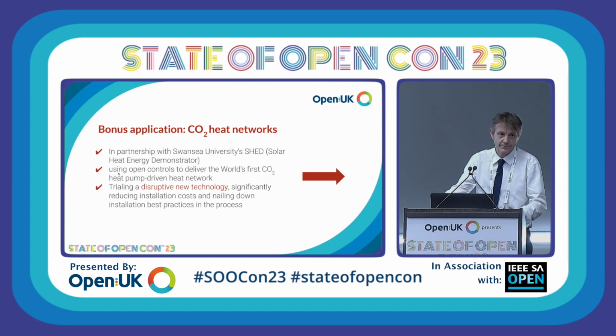In the heating world, you have consultants with professional indemnity, so they can't do anything that's not covered by regulations. We sit in a unique spot because we write the regulations. We wrote the CP1 guidance for heat networks, and we wrote the original plumbing guidance for the Institute of Plumbing. So we're in a technical position to take on these jobs, but the only way this job happens is by partnering with a university, so there's no consultants in the picture. We've designed a system to run a CO2 heat pump, which should allow us to get the cost of converting and retrofitting existing housing stock to about £5,000 a property.